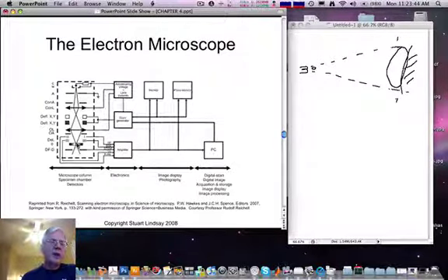However, by energy filtering and collecting just the backscattered electrons, another type of image can be formed. By collecting the transmitted electrons, a scanning transmission electron microscope image can be formed. By collecting light from semiconductor samples excited by the electrons, a cathodoluminescence image can be formed.